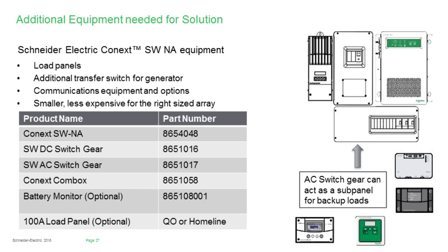The nice thing with the AC switchgear is it actually has some extra slots, so you can bring in some extra DIN mount breakers, and those DIN mount breakers will allow you to use that solution as your critical load panel. Of course, you do need to be aware of some of the limitations when we start putting together an AC coupling solution. That switchgear box may not have enough room to meet UL NEC listings for backfeeding onto it, so you may still need that 100 amp panel down below. There on the right-hand side, just to the right of the AC switchgear, can be used as a subpanel for backup loads.